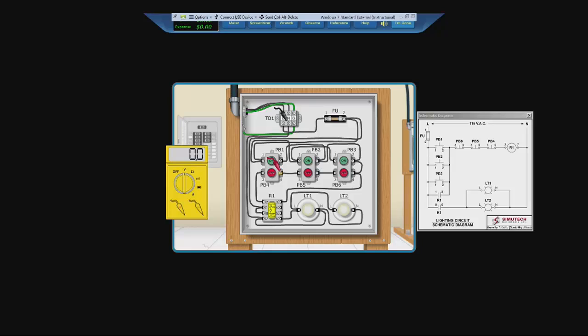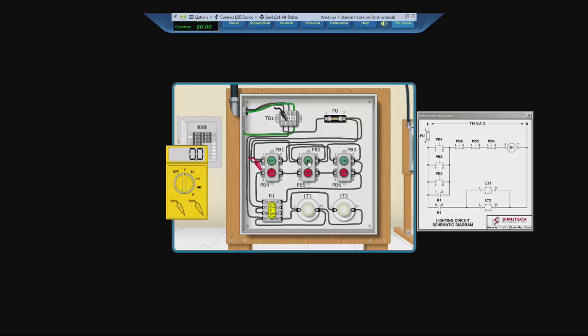So now let us go to here, push button four, the end right here. So if we've turned on power and we receive a voltage reading here, that means it's good. And obviously, since we are not receiving power here, it means there's something wrong in between.